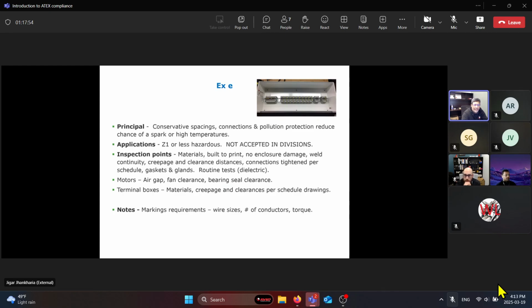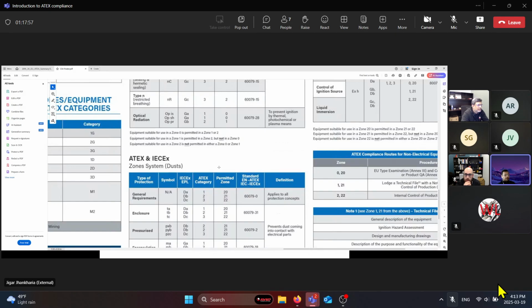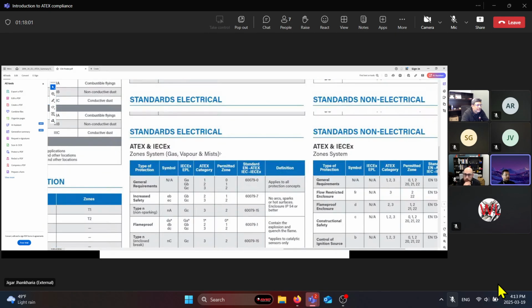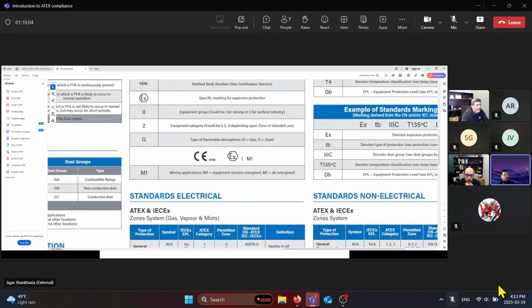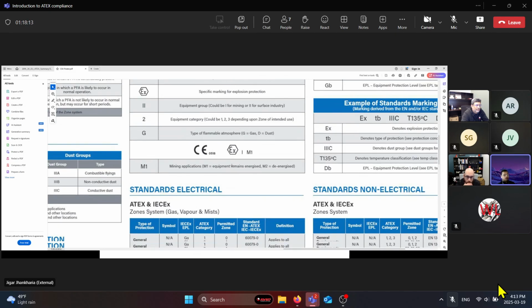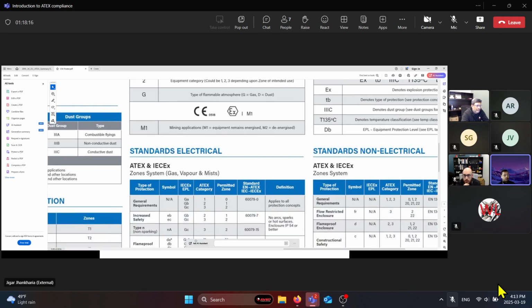What's the distinction between categories? Yeah, so categories and zones is basically, it's dependent on what zone the equipment is used in. The category is dependent on the zone marking. So if your equipment is certified for zone 1, for example, for increased safety, as you can see here, then they classify that as a category 2 equipment, where a category 1 or category 2 equipment would require the quality assurance notification and quality assurance report as per the annex and module A of the directive and IECEx.